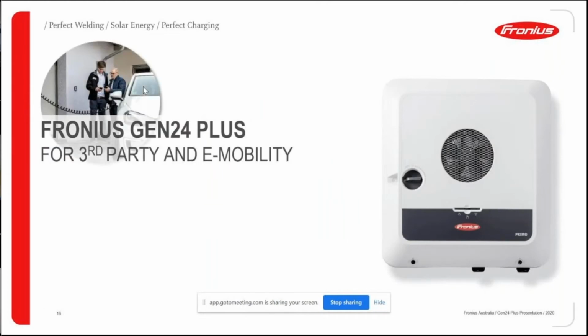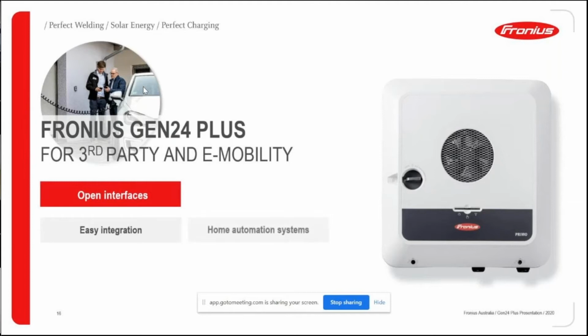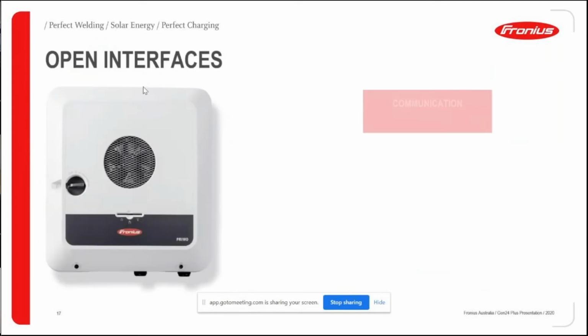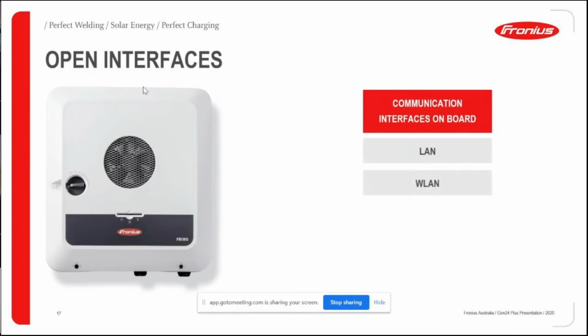All right, so the Gen24 has open interfaces, which means you're able to integrate the Gen24 with home automation systems and also EV charging stations. This is going to maximize the customer's self-consumption if they start getting smart about how they use their PV power during the day, especially if they don't have a battery as yet. It's got all the standard open interfaces that the Snap inverters had. It's got LAN and Wi-Fi and the Modbus connection for the smart meter, and there's also a second Modbus connection now as well.